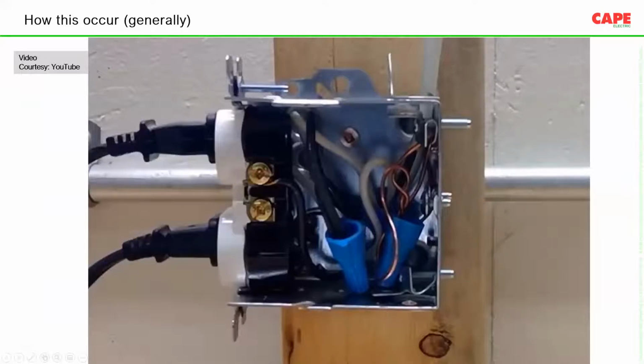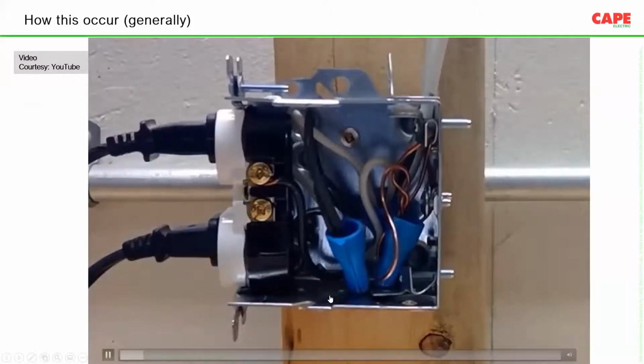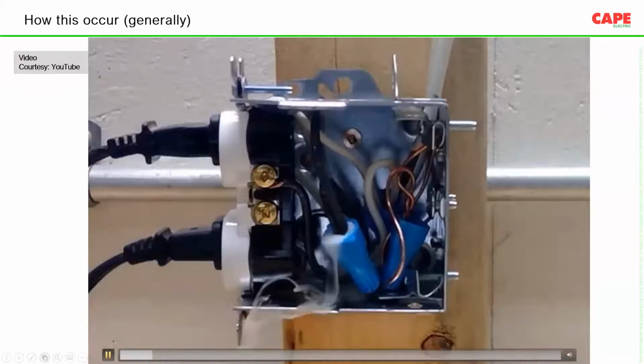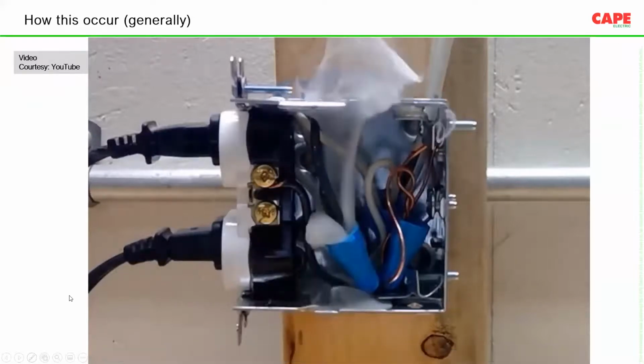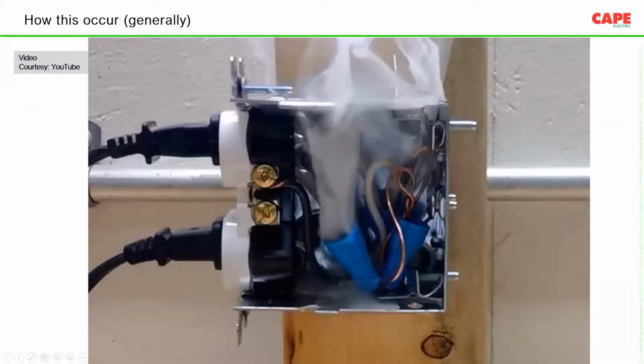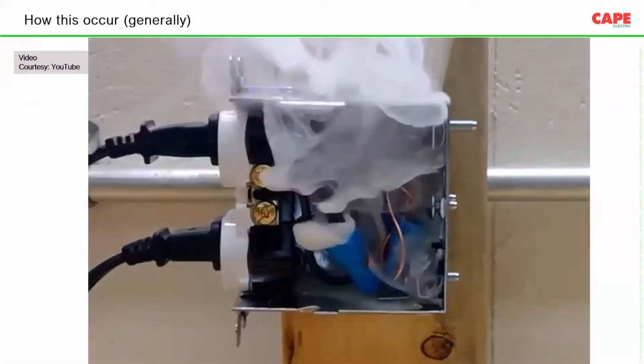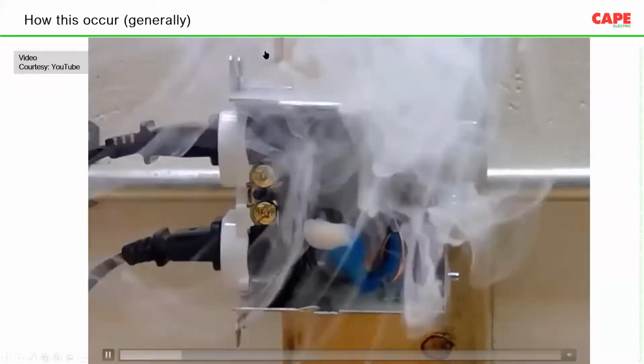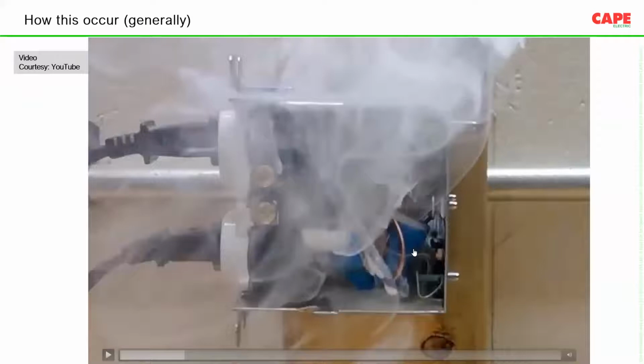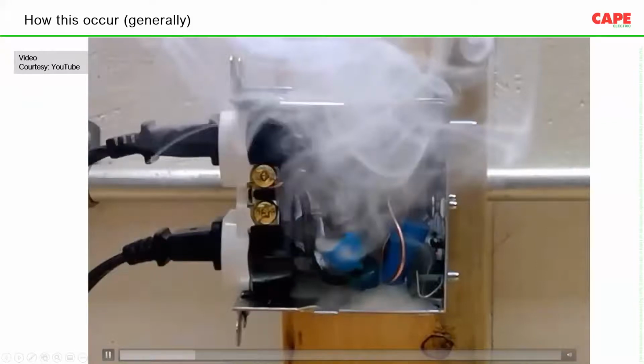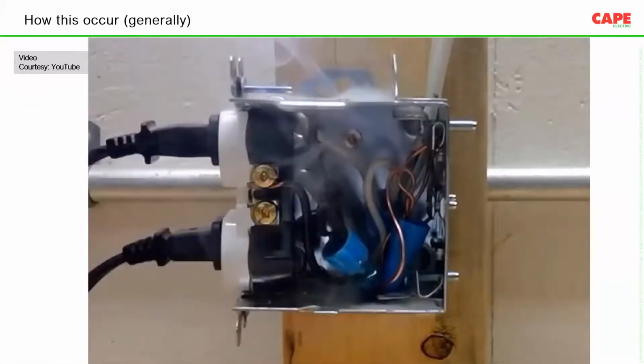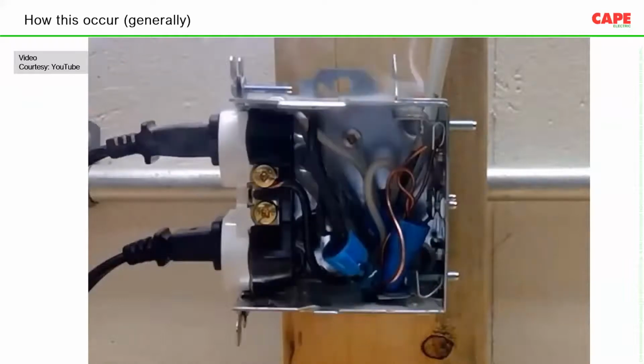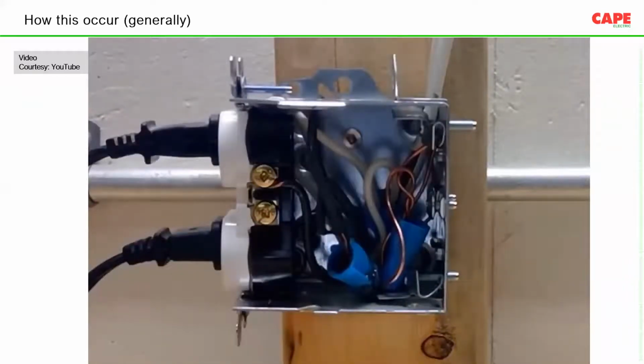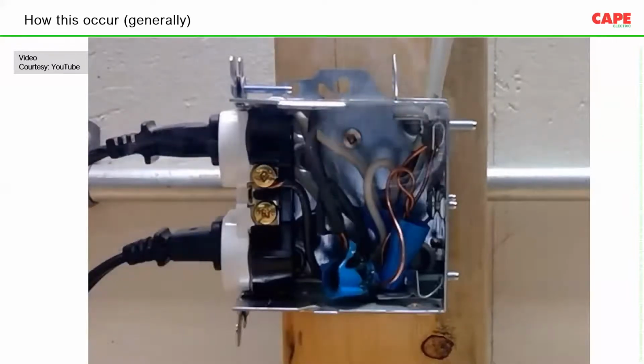Now here you can see another video. This I took from YouTube. You can see here a spark on the junction box. As a result of the spark, the insulation has gone. Higher current is flowing. The entire box is getting hot. As a result, smoke starts coming out. You see, from the time of the spark up to the time when this whole thing is igniting fire, there is a time. Probably in this particular case, maybe half a minute or more than half a minute. In the hospital case, probably it is a few seconds. But basically, we have time.